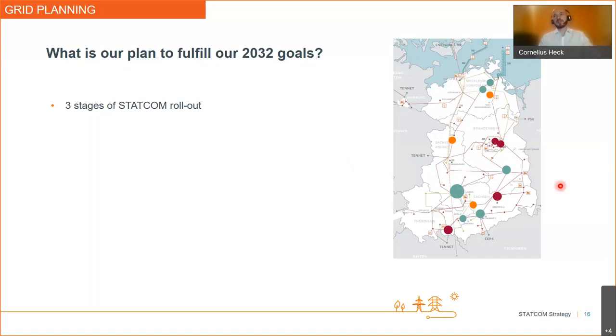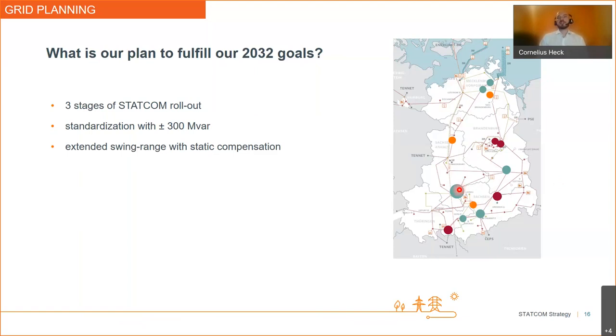And the size of the bubble obviously tells you how big the STATCOMs are going to be. But we are looking at a standardization of 300 Mvar STATCOM, where Roman is going to tell you a little bit more about. And some of these STATCOMs will have an extended swing range. So for example, in this location, we are looking at a STATCOM with additional MSCDN to have some more reactive power capability for under voltage situations. For all the STATCOMs that we are talking about here, we want them to be grid forming already, grid forming control.